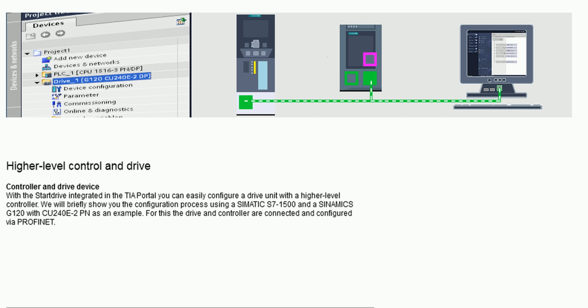Controller and drive device. With the Startdrive integrated in the TIA portal, you can easily configure a drive unit with a higher level controller. We'll briefly show you the configuration process using a SIMATIC S7-1500 and the SINAMICS G120 with a CU240E 2PN as an example. For this, the drive and controller are connected and configured via Profinet.